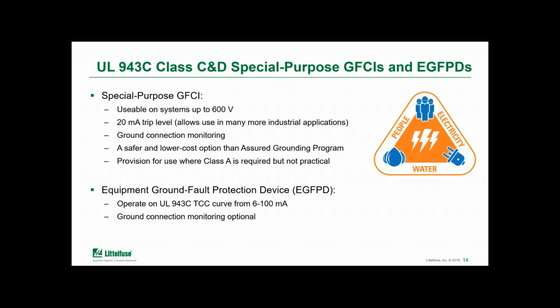Now, one additional requirement here is continuous monitoring of the ground conductor between the receptacle and the load. That really protects against a hazardous voltage on the chassis of the load if there is a problem with the ground conductor or an open circuit in the ground return. In the US, that's really what the OSHA Assured Grounding Program is all about. A special purpose GFCI with this function allows you to automate that and continuously provide that protection. If you compare that to the manual effort required for ground proving, and how often ground proving may be done, the automated solution can certainly be more cost effective and provide safety that's monitoring all the time.